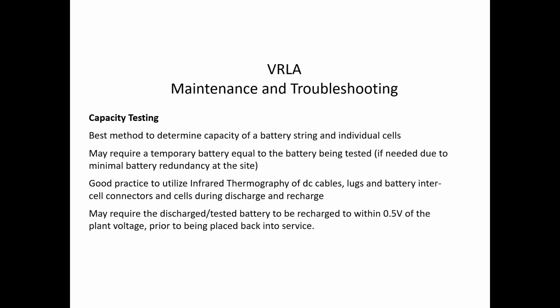Again, you want to run that battery all the way out to the designed end so you can see that curve, because the battery could look like it's doing well initially, but it could quickly, for lack of a better term, run out of gas. You get halfway through the test and you can see that sometimes. Some batteries, depending on the failure mode, will look really strong and then halfway through they'll just dive. And you won't get that with just a snapshot of the front end of the load on the battery.